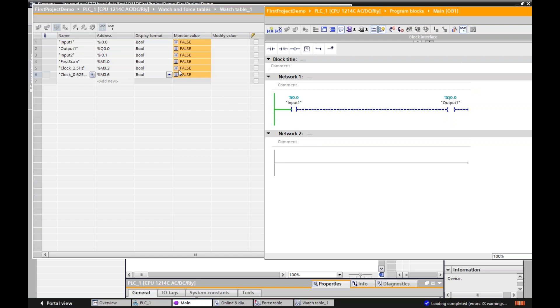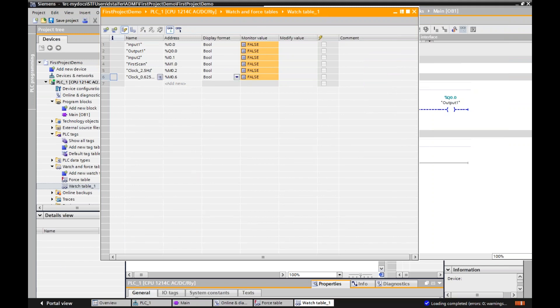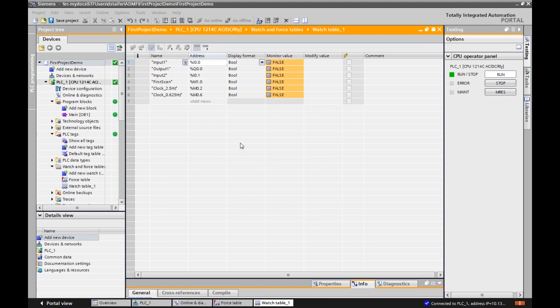I don't know why these clock bits aren't working as they should. I downloaded my hardware — I may have to re-download my hardware configuration. Yes, I had to re-download my hardware configuration. Because in this case, I just went in and clicked those boxes and downloaded, but because this is a hardware change, you need to rebuild your hardware and re-download it. So to get these clock bits active — and you can see them flashing now — that's how you would do that. Just because something is there in your tags doesn't mean it's active; if they're not working, you would have to re-download your hardware configuration. Now we can watch these things.